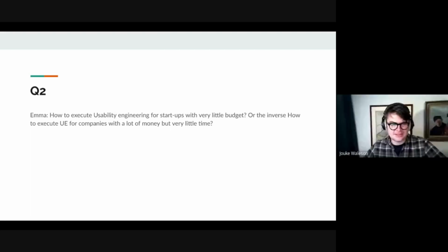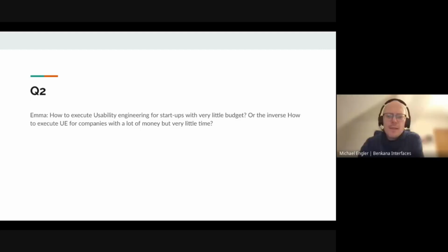Michael? The best thing to get cheaply through usability is starting as early as you can. And that means before you even write down an intended use, before you even think about a device, start usability engineering. Get to know your users, get to know the use environment, and you'll be much cheaper off because you remove loops.